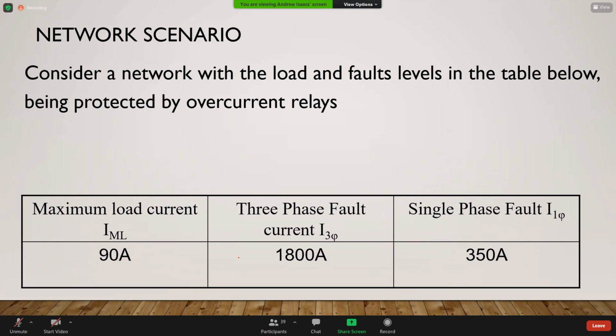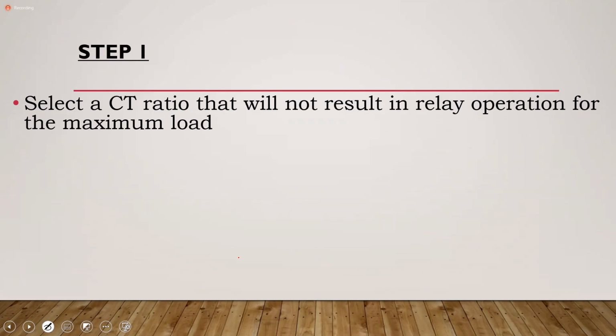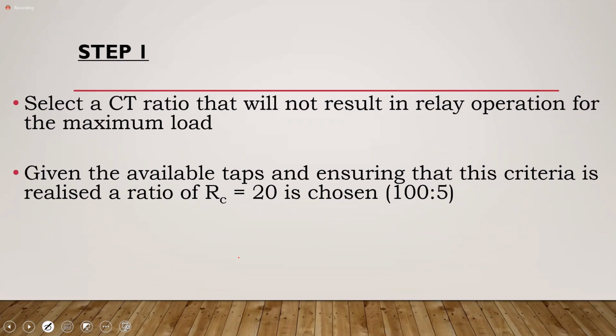Yes, sir. All right. So first step: we're going to select a CT that will not result in relay operation for the maximum load. Now, part of this is that you are also going to select the tap. The main focus here is not on the CT, even though, as an engineer, you would have to take note of the CT that you use. But for our purposes, we are going to give you the CT. You with me? So although I say select it, I'll give that to you. It's not something you would have to worry about. But it's important from a protection standpoint that we do that analysis, but we're not going to do it today. So we're going to use a CT ratio of 100:5.